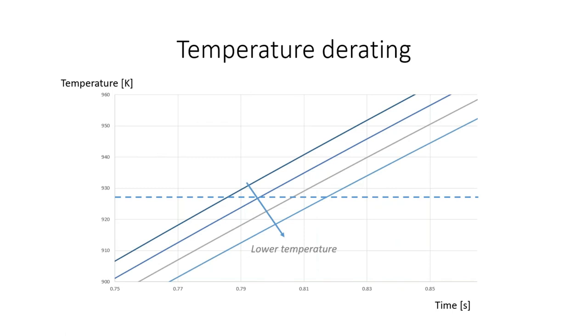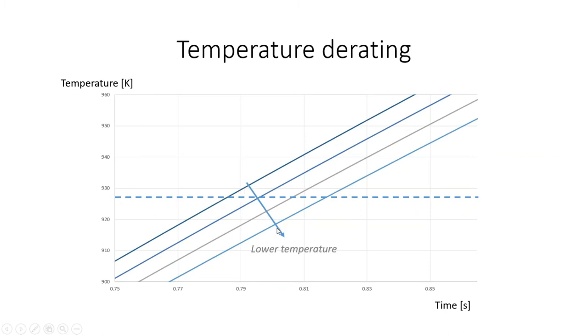Now let us look at the temperature derating. If we plot the temperature rise curve for a few different ambient temperatures but for the same current, we'll again see that the lower the temperature is, the more time it takes to reach this melting temperature of the aluminum, which is very important to know based upon the ambient in which the fuse is going to operate.